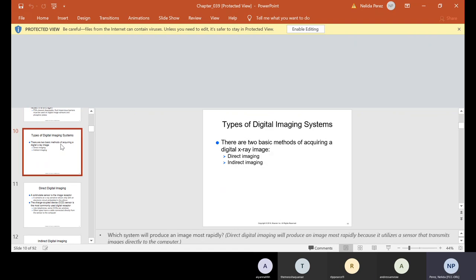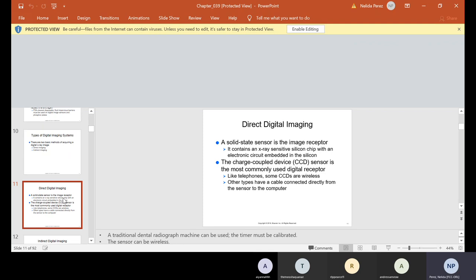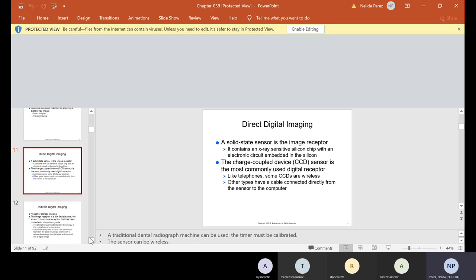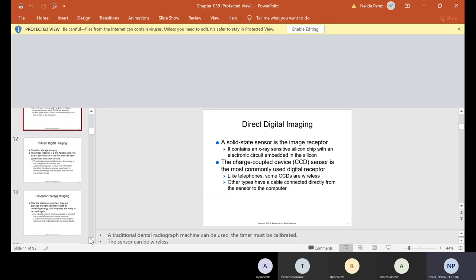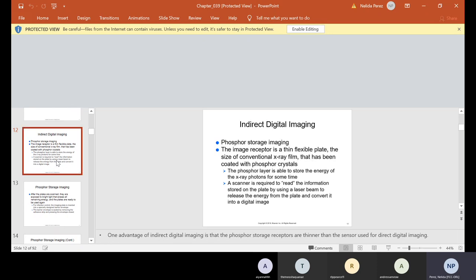There are two basic methods of digital imaging systems: direct and indirect. With direct, a solid-state sensor is the image receptor. It contains an x-ray-sensitive silicon chip with an electronic circuit embedded in the silicon. The charge-coupled device, or CCD, sensor is the most commonly used digital receptor. Like telephones, some CCDs are wireless, while others have a cable connected directly from the sensor to the computer — which is what we have.